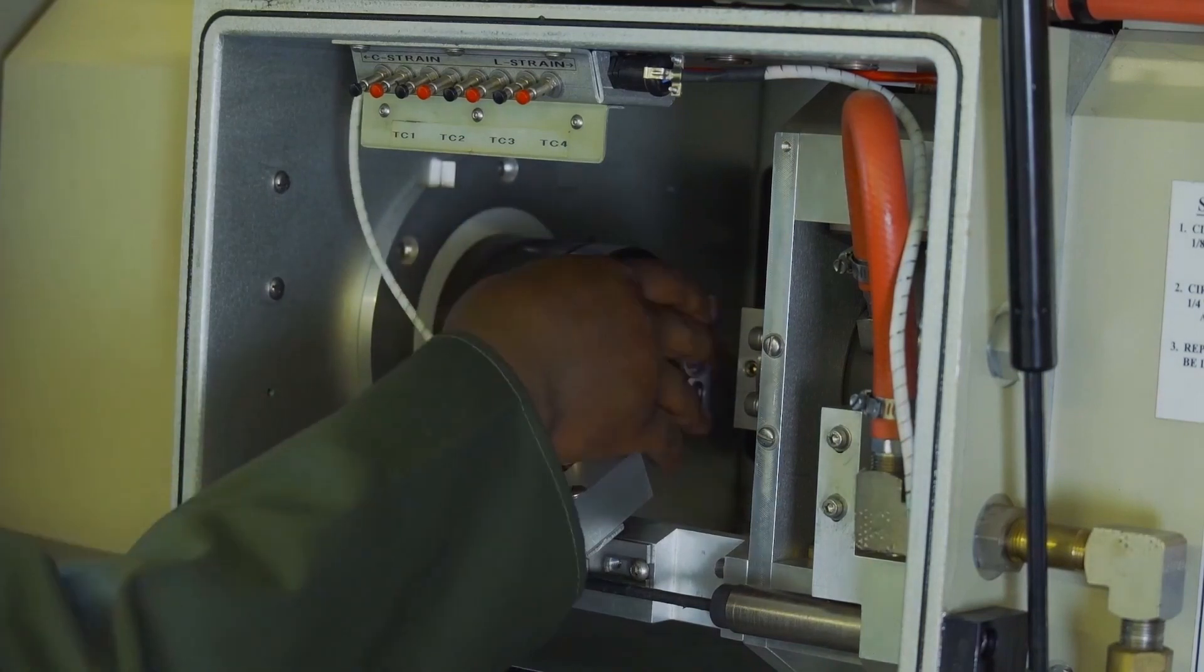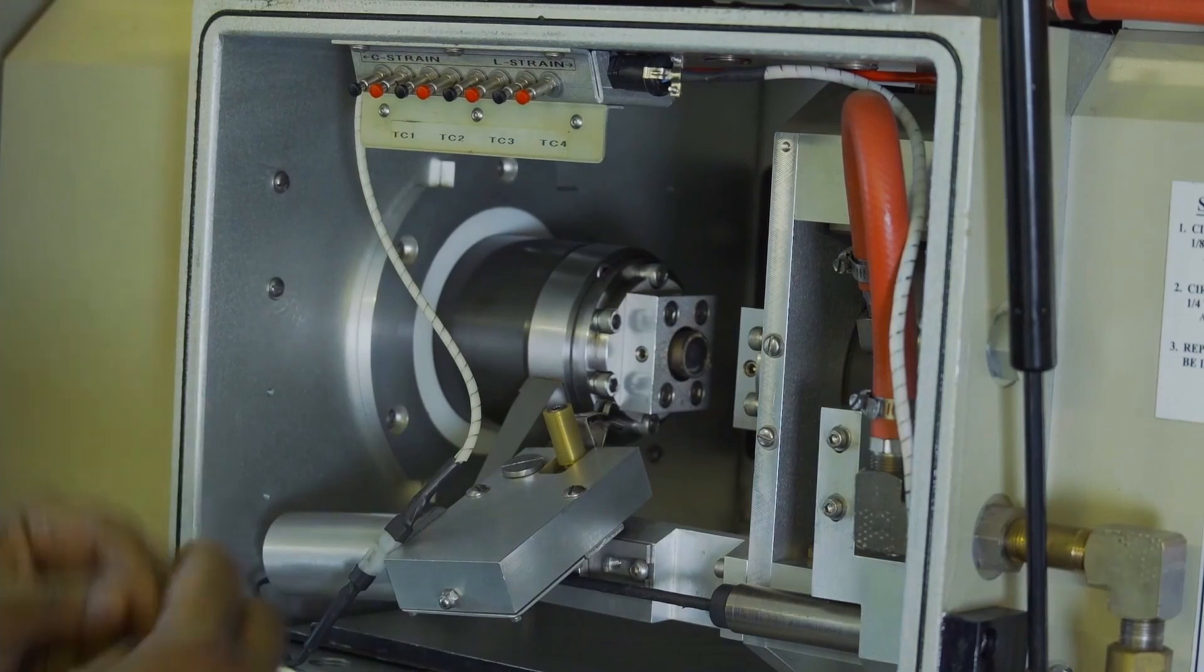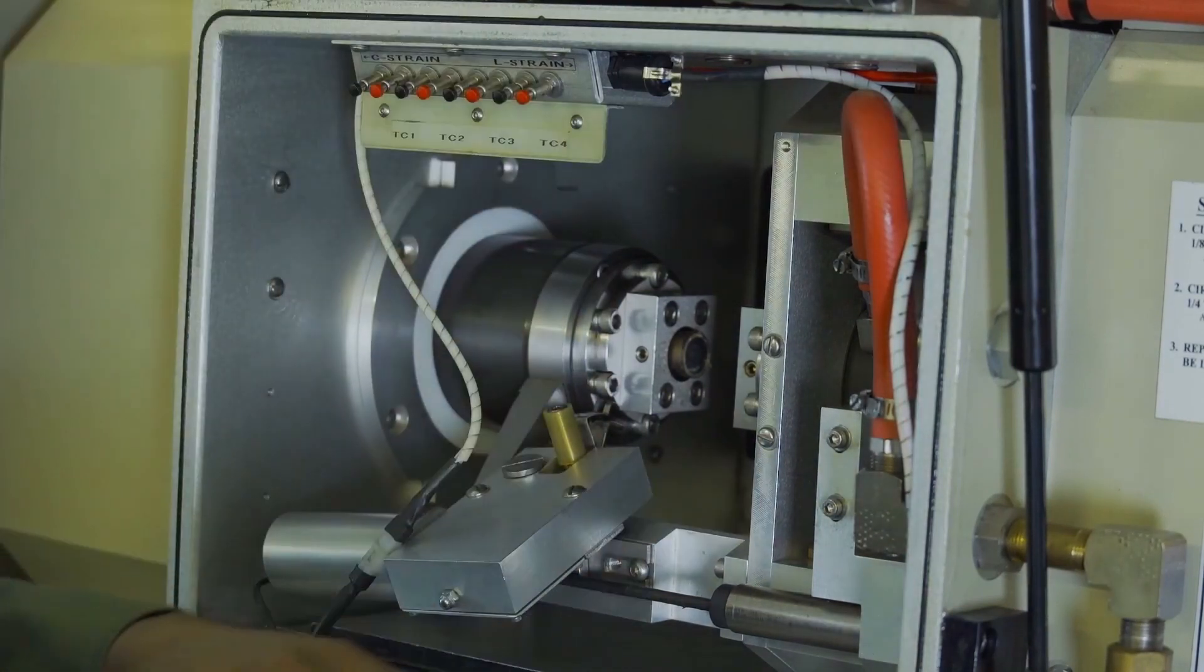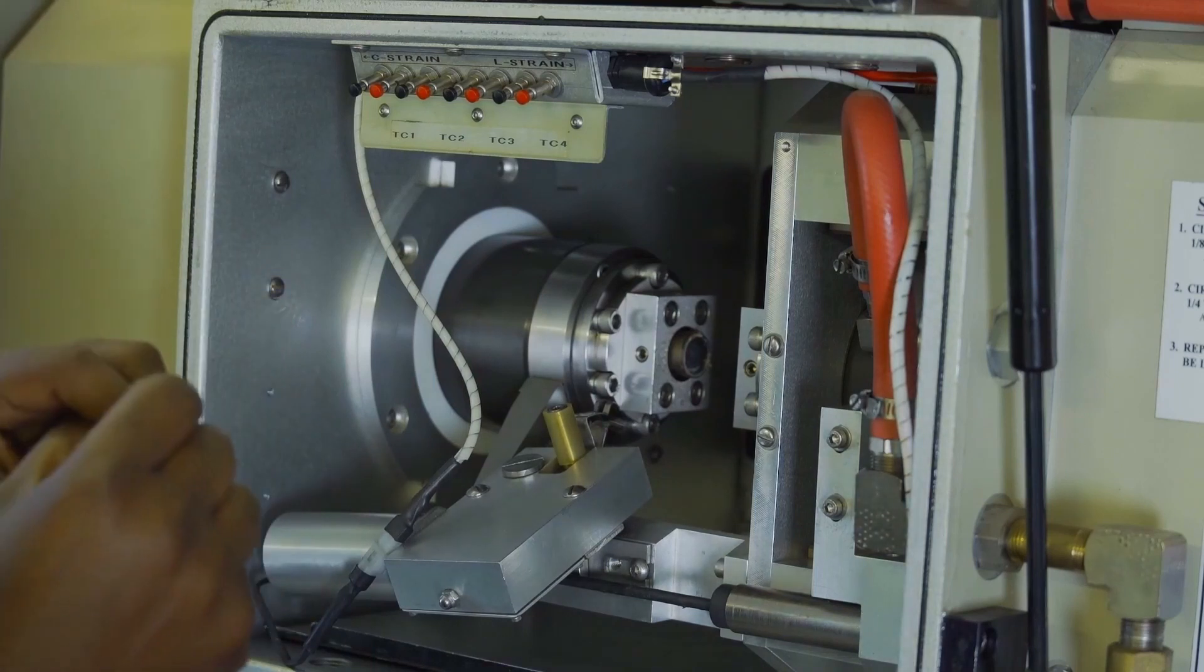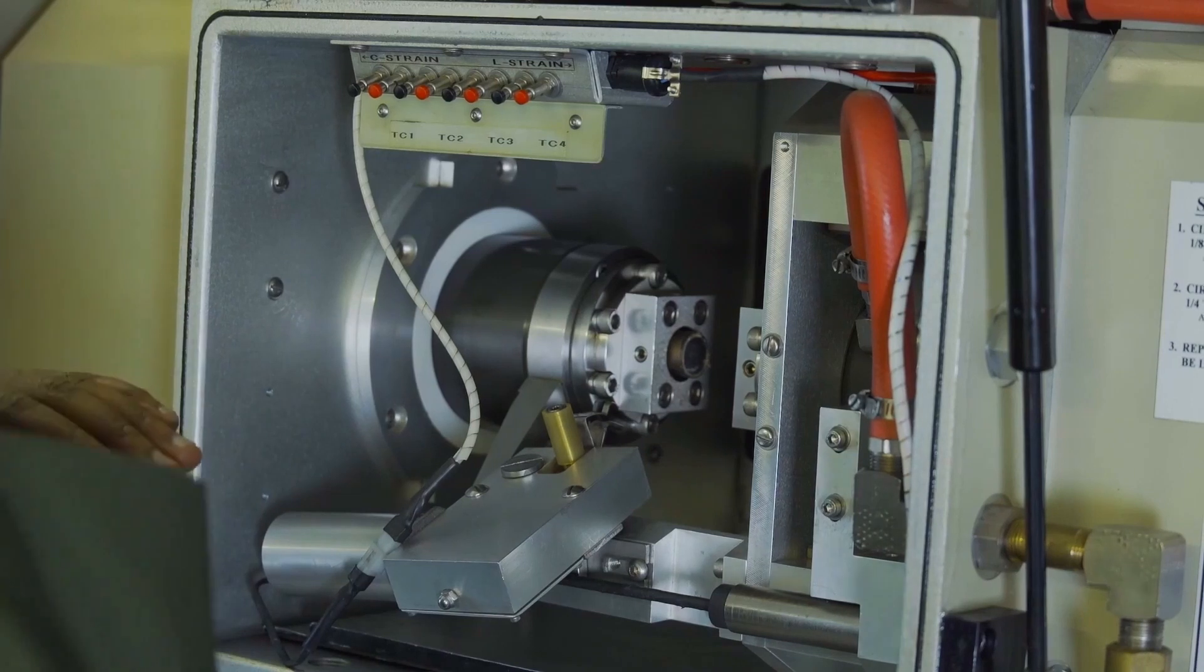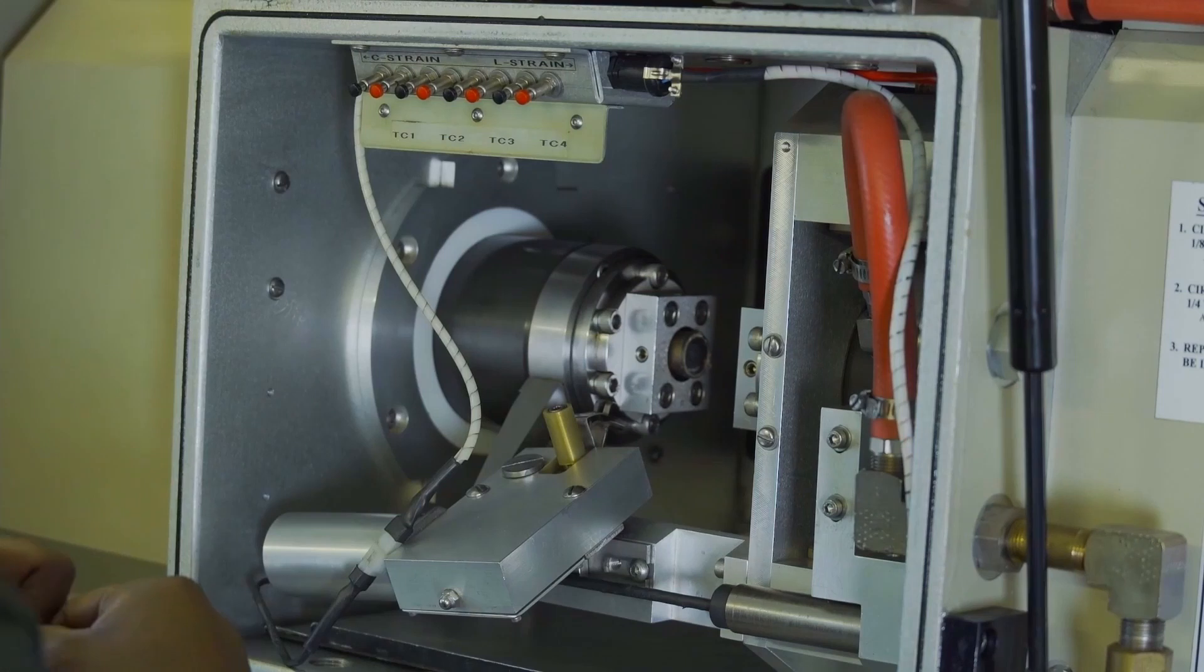The next thing I'll do is apply a lubricant on the surface of the anvils. Why do you need to apply a lubricant? Because you want to minimize the effect of friction on your results. Once the anvils grip the sample, they exert some frictional force on it, so you need lubrication so that wouldn't affect your flow stress.